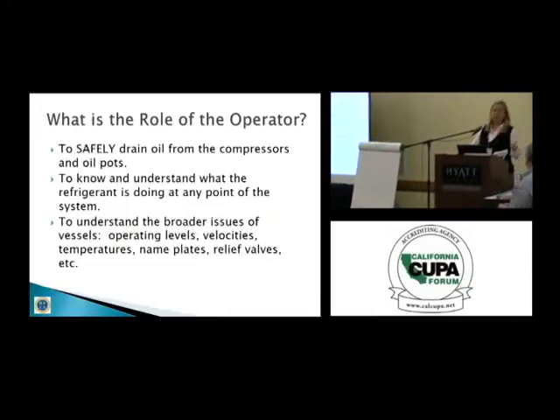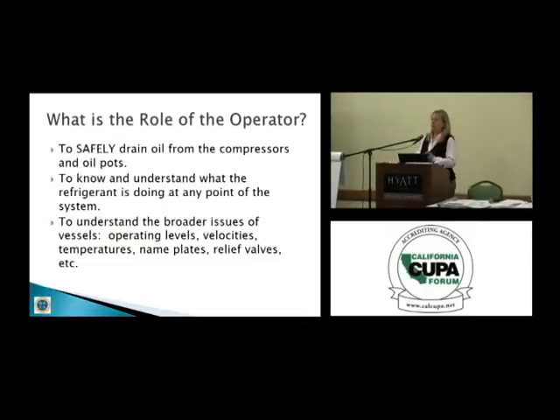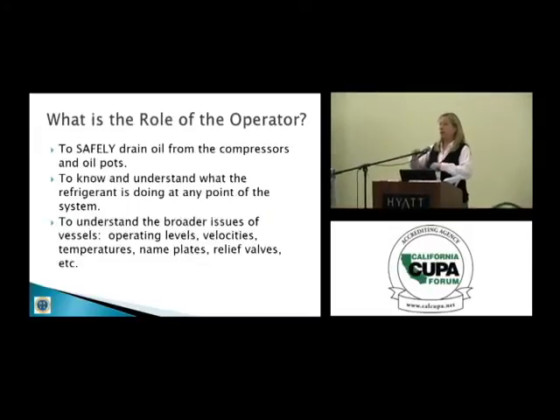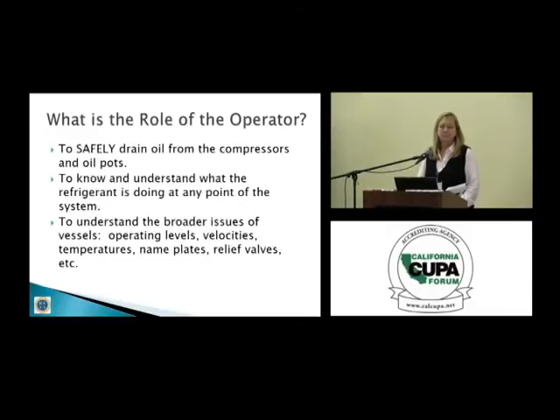They can also back engineer. Ransom actually has done that, and back engineer if there's no U1A and no plate, for a really old, pre-1950-ish vessel, they'll actually go in and x-ray and they can back engineer the whole thing. It's expensive, but it can be done. Yeah, I've seen them do it. As a businessman, you have to look at the practical options. New vessel replacement versus the reverse engineering and certification. It all depends. It all depends.